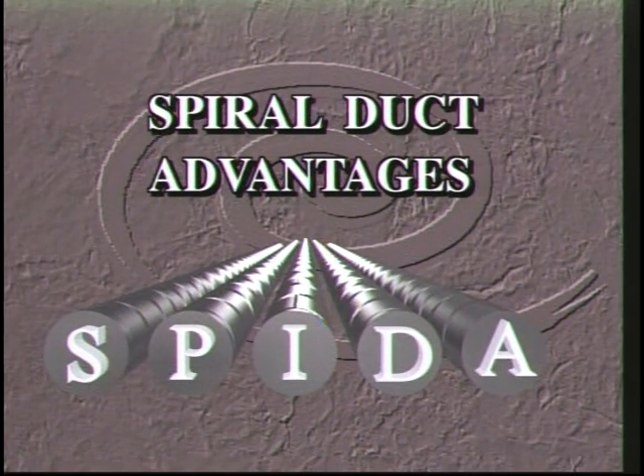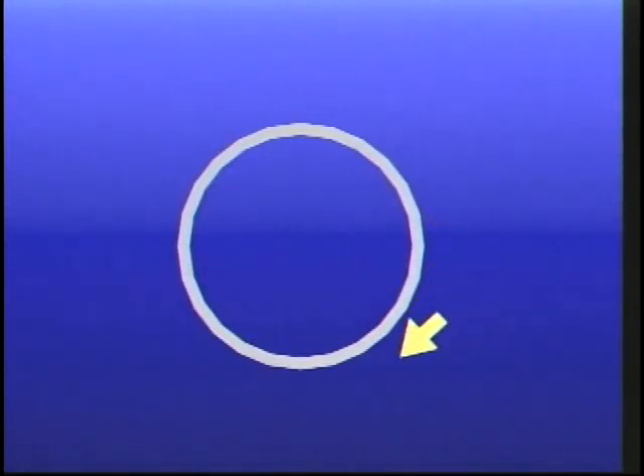HVAC duct sizing tables are based on round duct sizes. For example, the hydraulic round duct size equivalent to a 22-inch by 22-inch square duct is 24 inches in diameter. The round duct has 6% less area and 17% less perimeter. The 24-inch diameter round spiral duct also is equivalent to a 35-inch by 14-inch rectangular duct or to a 60-inch by 10-inch rectangular duct. The 60-inch by 10-inch duct has 32% more area and almost twice the perimeter of the round duct.